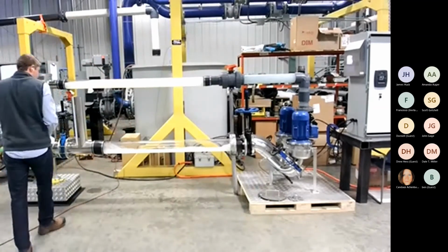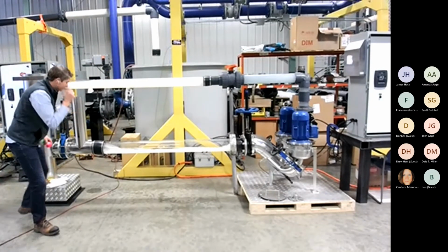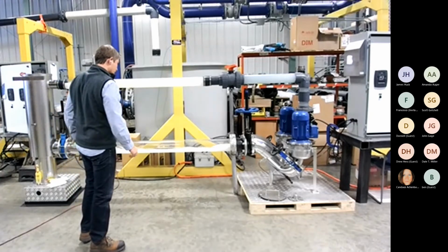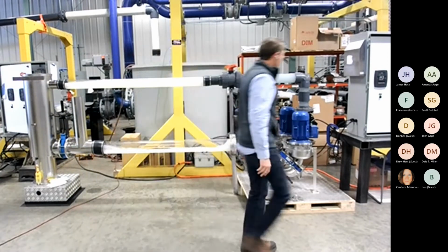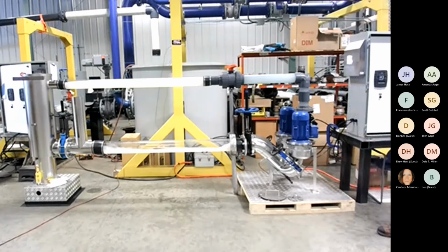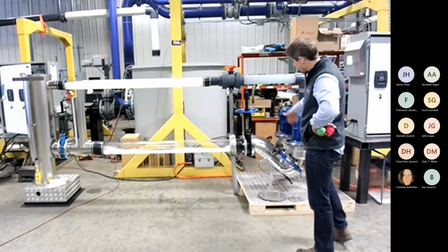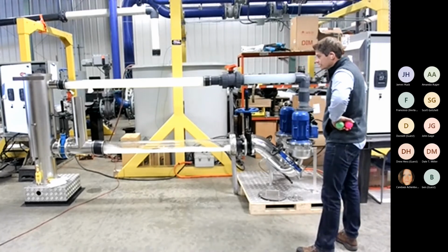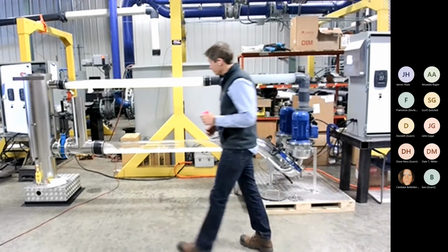So let me go back. It looks like the system is pretty close to regulating. I'm running at 40, looks like 44 hertz right now. So obviously just one pump, and we are regulating right at 9 inches. So I had the regulating point here at 9 inches - it turns off at like 6 inches, and turns on at like 20 or 25 inches.